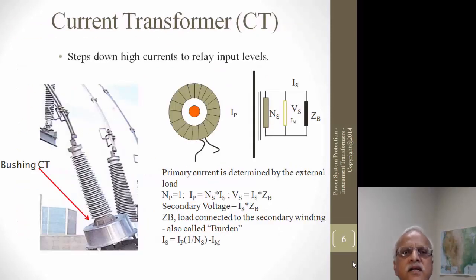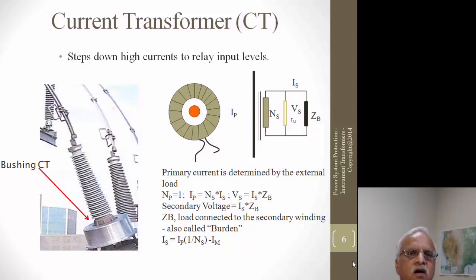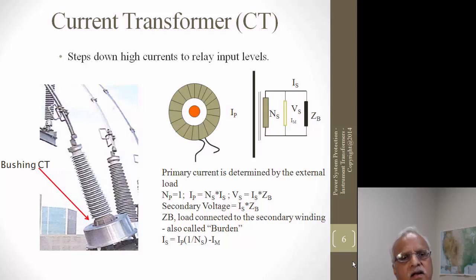In the case of a voltage transformer, the primary current is determined by the load connected on the secondary side. In the case of a current transformer, it monitors the current going on a transmission line or through equipment, so it has no control over the amount of current flowing through it — that is determined only by the external load. The primary normally has only one turn.